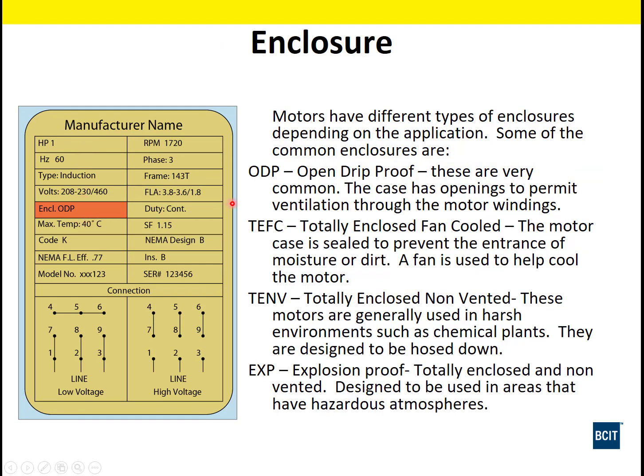We have the enclosure type. Here we go, a whole list of them. We talked about this at the very beginning. Open drip proof permits it to be ventilated through the motor windings. Outside external air ventilation can go through. Totally enclosed is a totally enclosed motor with a fan on the end. Then we have totally enclosed non-ventilated. Those guys have no external fans.